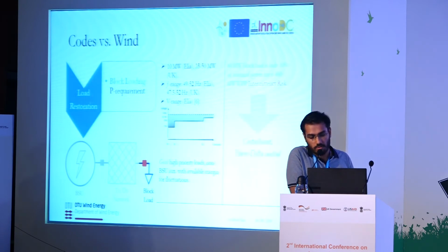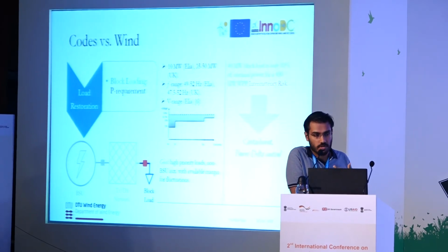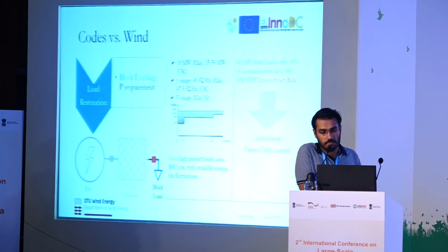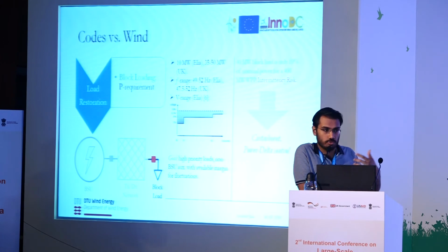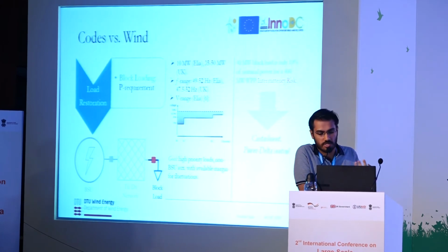Ultimately, picking up block load, which for example in Belgium is 10 megawatts, for UK it's about 40 megawatts. This is for a 400 megawatt farm with maybe good or almost rated power production. This is not really a big deal. However, what's important is to maintain stability of operation and thus controlling the voltage and frequency within stable operating range. And for this, some sort of a curtailment is required. Some grid forming capabilities are essential. That I'll also talk about in the next presentation and show some initial results.